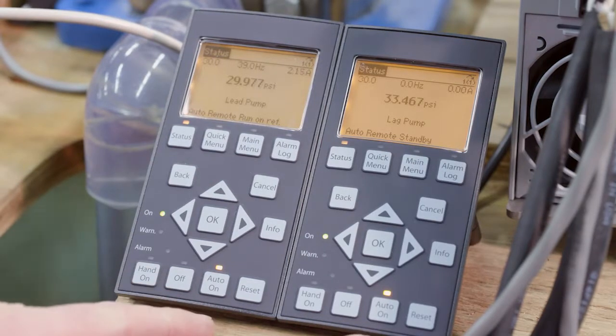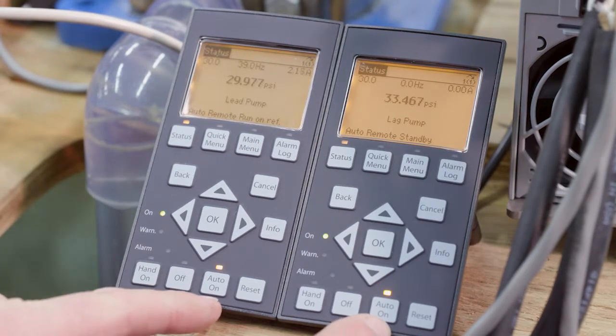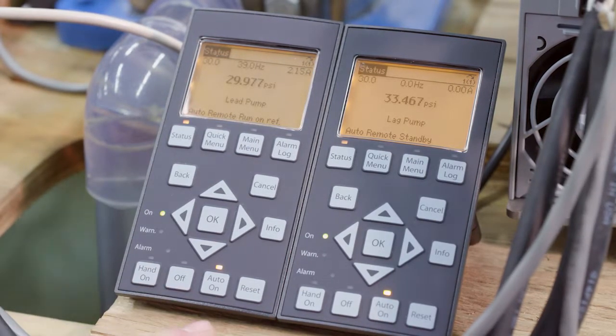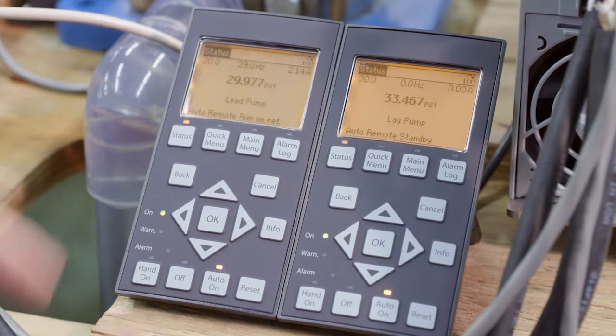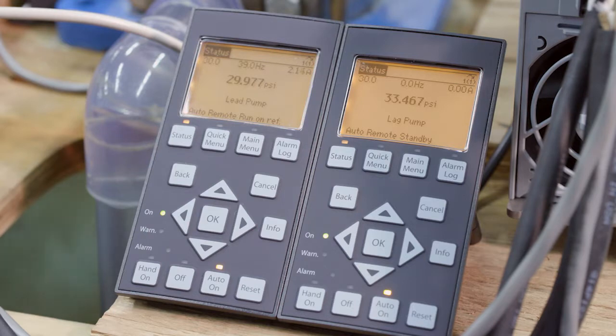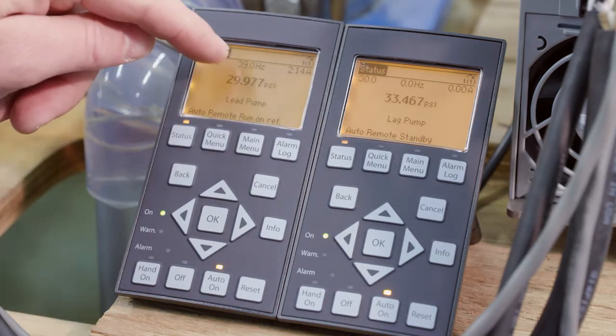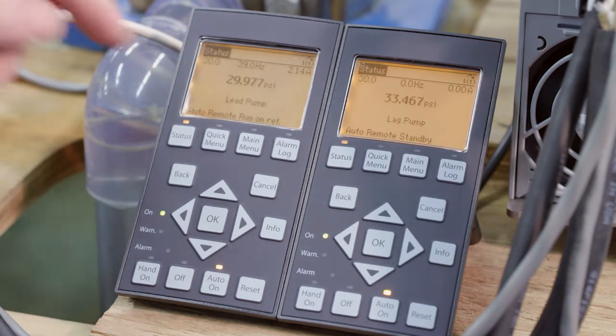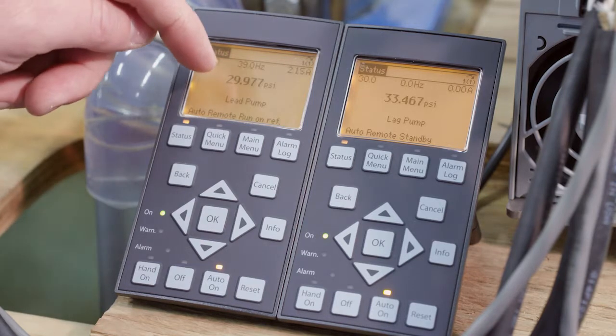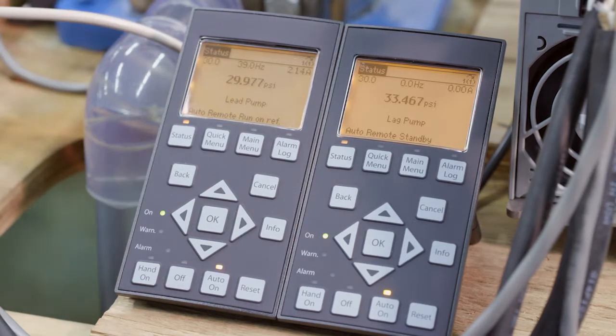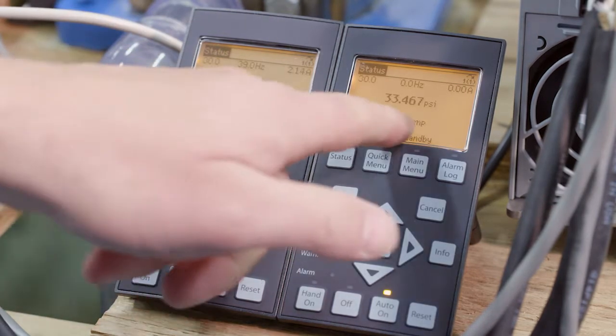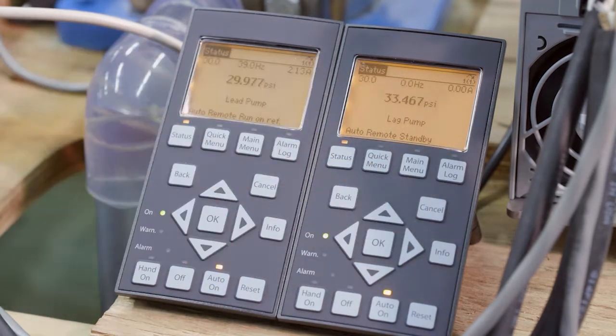So what I did was I hit the auto on button on both and I opened up my discharge valve, and notice we can see a lead and a lag. And we see the lead pump is at 39 hertz. It is meeting our set point of 30, and our lag pump is not running right now.